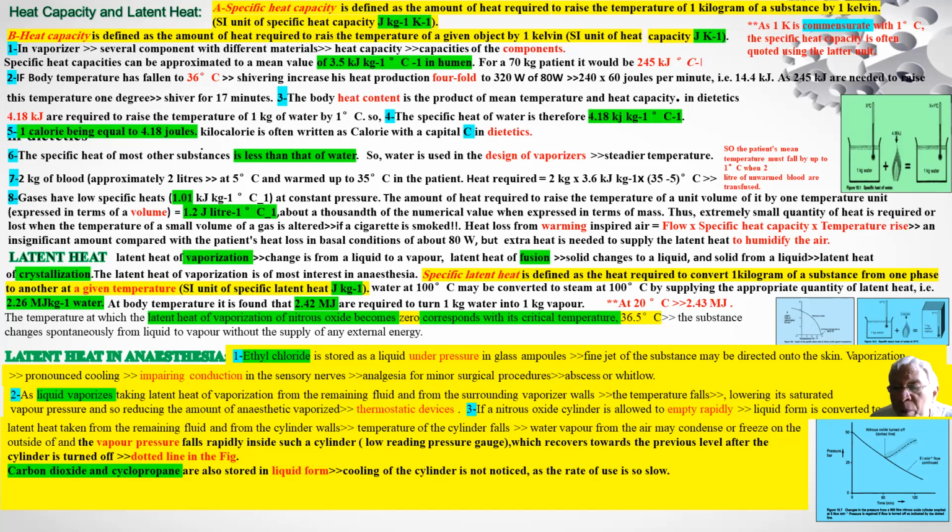In vaporizers, of course, each of the components has its own heat capacity, so we can calculate the total amount. And we said it before in vaporizers. This is the specific heat of the human being, which you must memorize, is 3.5 kilojoule for each kilo, for each Celsius. You see, the total is rated on the other side whenever we mention a patient with 70 kilograms weight.